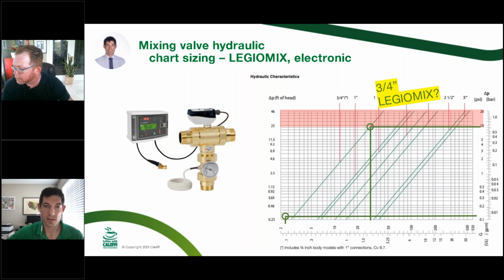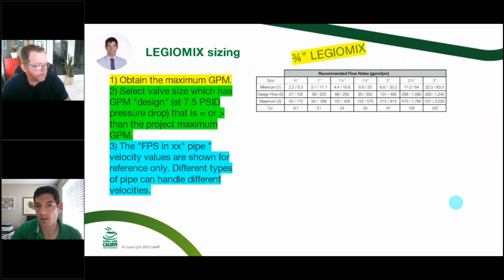We've got great CVs through these valves, and it's a reason that if you started with the 1.5 inch trunk piping and selected a 1.5 inch LEGIOMIX, you're going to be way oversized. And we've got another sizing way to show that on upcoming slides. That's a simplified version of this. But if you really want to get into the weeds and make sure that you're doing the calculations properly, I'll walk through the chart on this slide here.